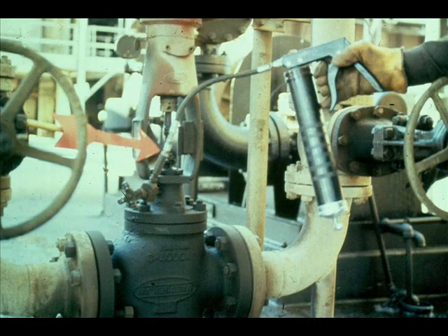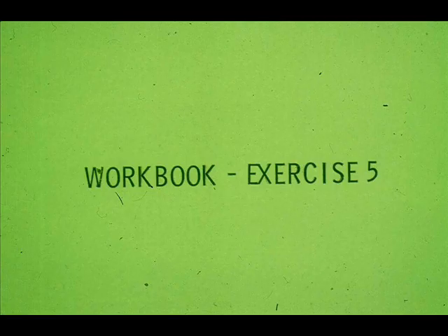The Rutherford lubricant is a Teflon-based paste that actually forms a packing. It can be installed in a valve by using a Zerk fitting and a grease gun. At Baytown plants, this lubricant has been pumped into leaking valves and prevented valve or unit downtimes. Now, work exercise 5 in your workbook.